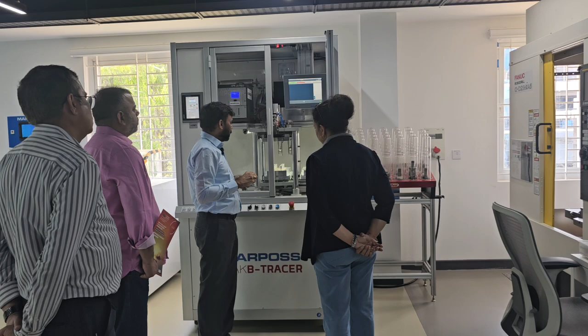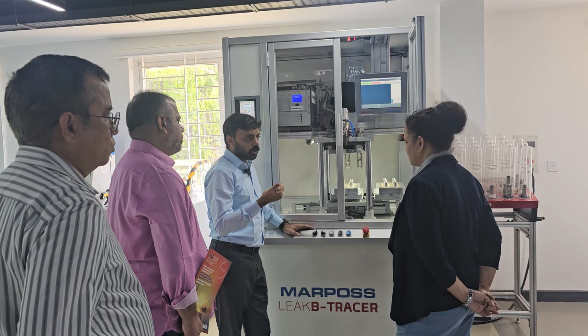It can be used for both lead acid and lithium ion batteries, majorly lithium ion being the latest technology. In the cell construction, they have a cathode, anode, and electrolyte filled inside the battery. When that electrolyte is filled inside, they seal it with welding and other methods, so they have to check whether the electrolyte is properly filled inside and whether there's any leakage outside.